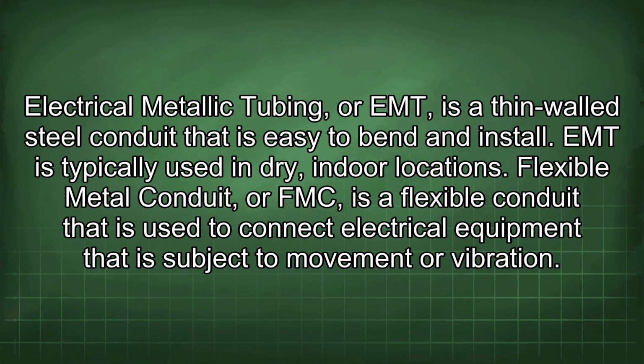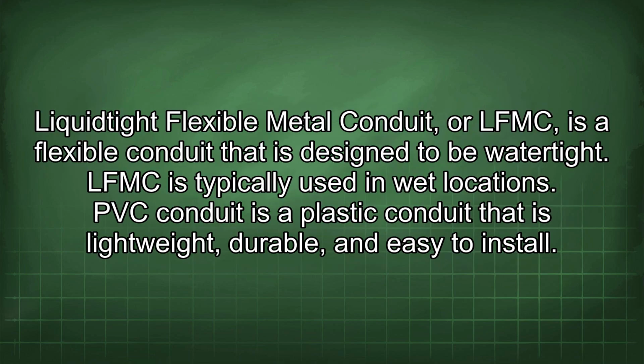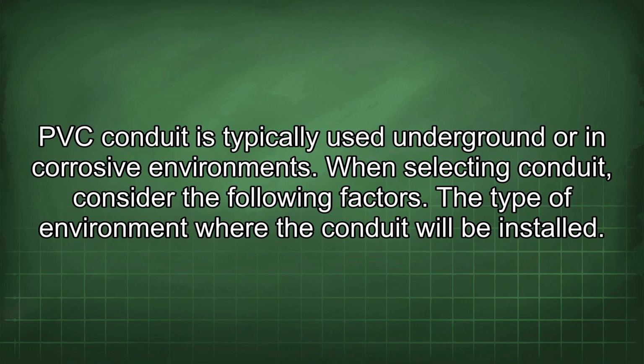Electrical metallic tubing, or EMT, is a thin-walled steel conduit that is easy to bend and install. EMT is typically used in dry, indoor locations. Flexible metal conduit, or FMC, is a flexible conduit that is used to connect electrical equipment that is subject to movement or vibration. Liquid-tight flexible metal conduit, or LFMC, is a flexible conduit that is designed to be watertight. LFMC is typically used in wet locations. PVC conduit is a plastic conduit that is lightweight, durable, and easy to install. PVC conduit is typically used underground or in corrosive environments.